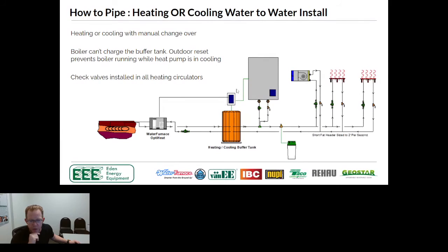So in this case, I'm showing a standalone control, which is true. IBC has their own standalone control. And in the case of the System M and the Enertech, a lot of this is built into it. But I'm going to show you guys in the next segment when I go to our live fire lab. The big takeaway point I want you to see here is this boiler. I could have put the boiler on this side, and then it would be feeding the water into the buffer tank. What I never want to have happen is to get this buffer tank up over 140 degrees, because then the boiler could superheat my buffer tank, and now inadvertently my outdoor unit, whether it's a water to water or an air to water, is getting superheated with water it doesn't need.